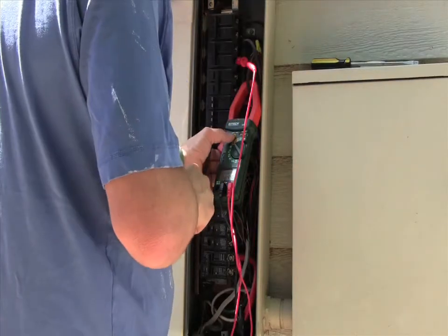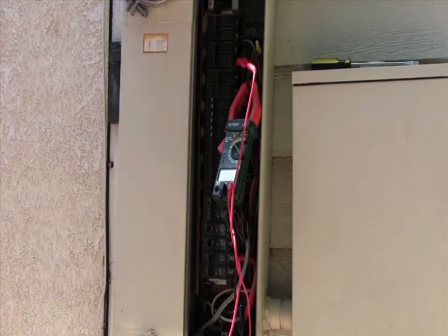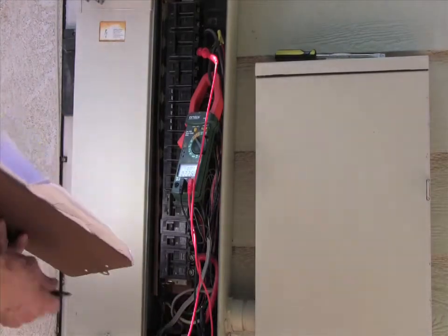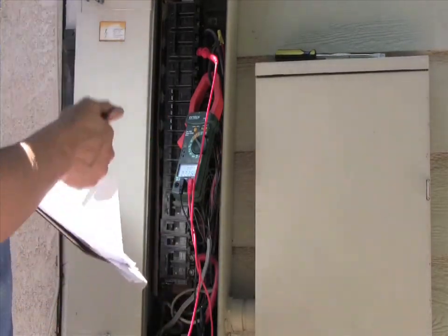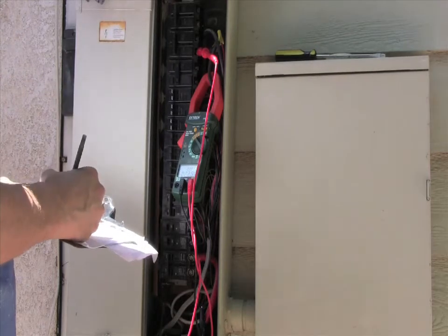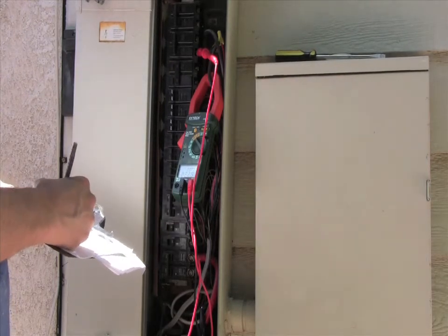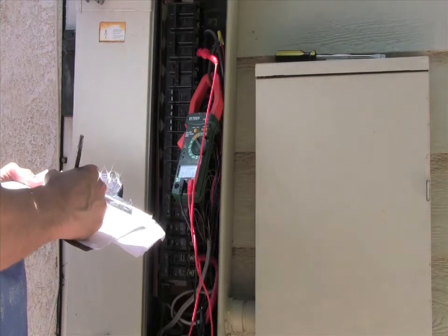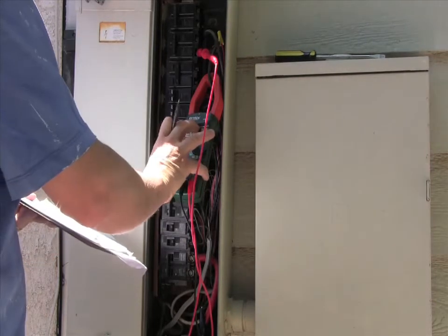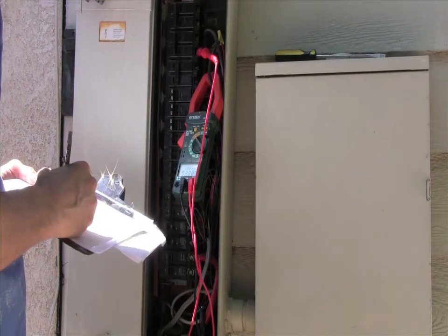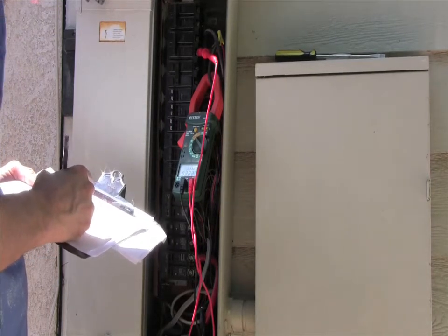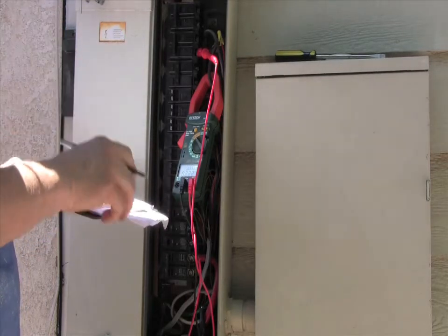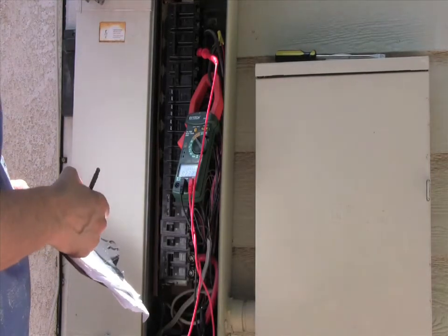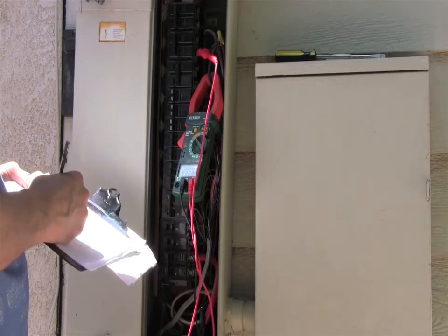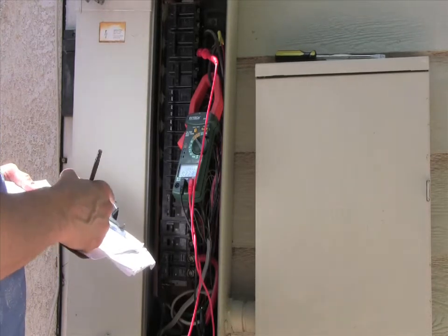Get back on that one right there. 30 seconds to calibrate. Alright, so it's been 30 seconds. So let's look at this one here. We got a horsepower of 3. Well, now it's 2.99. And 2.22 kilowatts. 0.994 lag, the power factor.